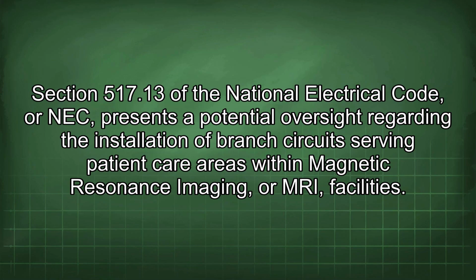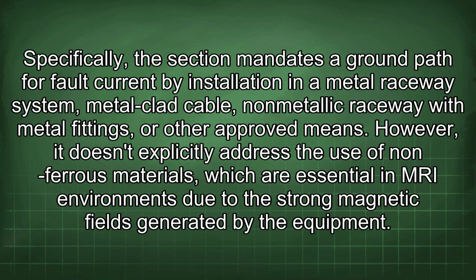Section 517.13 of the National Electrical Code, or NEC, presents a potential oversight regarding the installation of branch circuits serving patient care areas within magnetic resonance imaging, or MRI, facilities. Specifically, the section mandates a ground path for fault current by installation in a metal raceway system, metal-clad cable, non-metallic raceway with metal fittings, or other approved means.